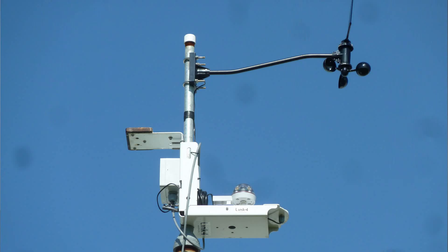The weather station from the retractable roof system has a rain sensor, a wind sensor, and a barometric pressure sensor. Where hail is a frequent risk, barometric pressure normally drops before a hailstorm. So we measure the change in barometric pressure, and we can automatically close the roof if it changes rapidly in a short period of time, helping protect the plants from hail damage.